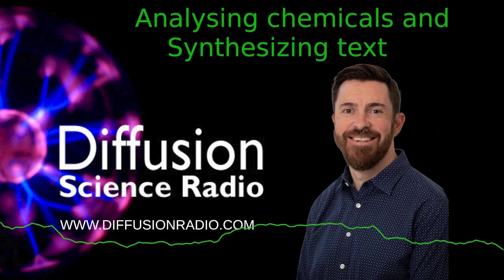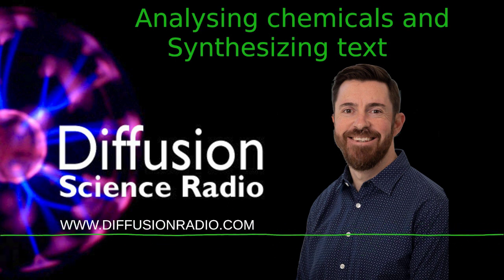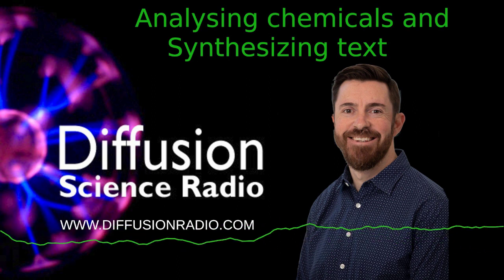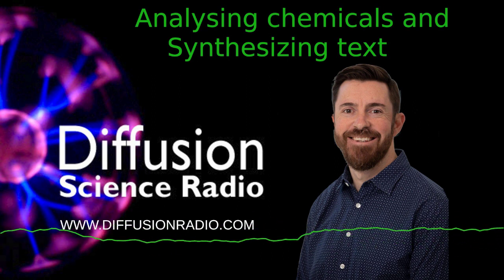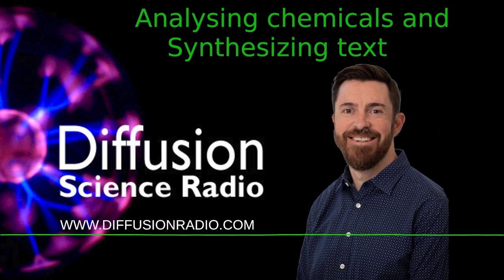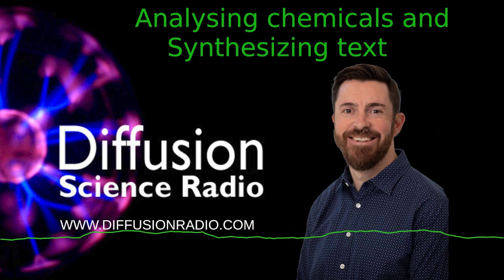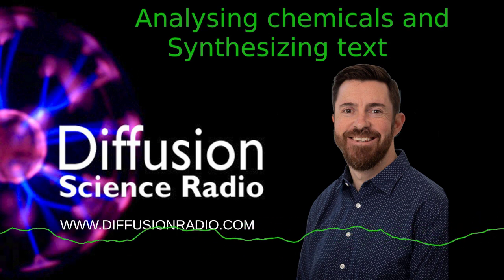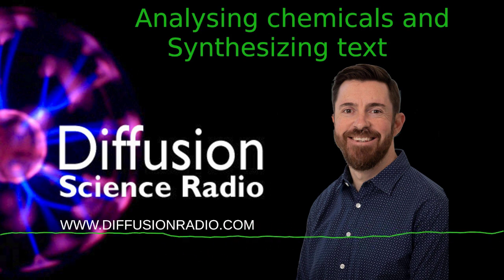So after the ions leave the mass analyzer, the quadrupole mass analyzer, they hit what we call a dynode array detector, where as the ion hits the first dynode, it sends out a cascade of electrons and it'll hit a series of dynodes, and each dynode hit will magnify the number of electrons going through.